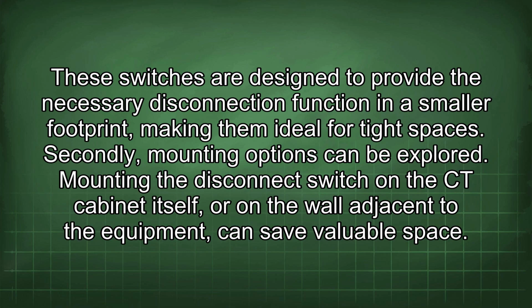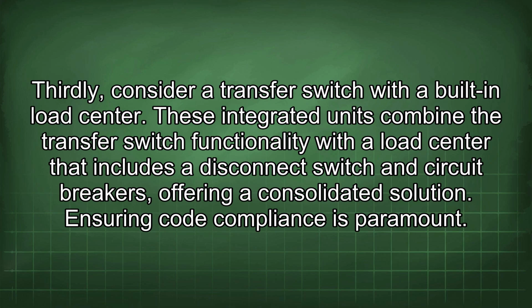Secondly, mounting options can be explored. Mounting the disconnect switch on the CT cabinet itself or on the wall adjacent to the equipment can save valuable space. Thirdly, consider a transfer switch with a built-in load center. These integrated units combine the transfer switch functionality with a load center that includes a disconnect switch and circuit breakers, offering a consolidated solution. Ensuring code compliance is paramount.